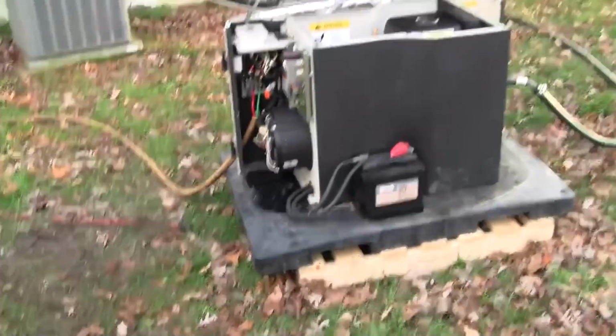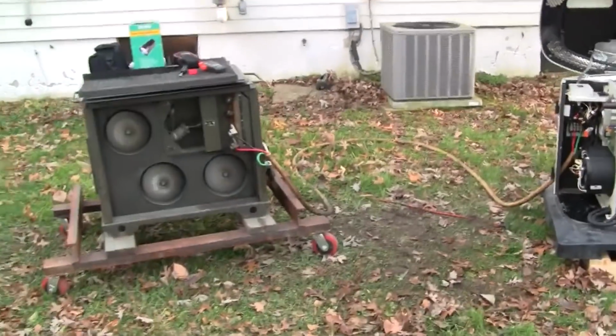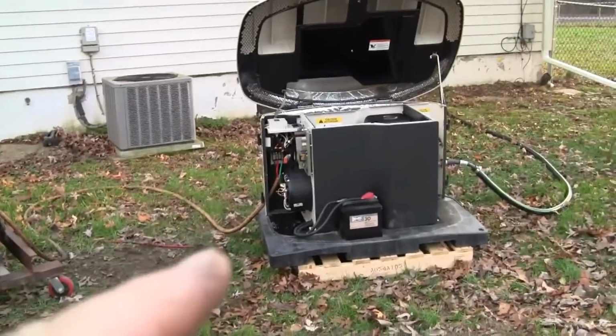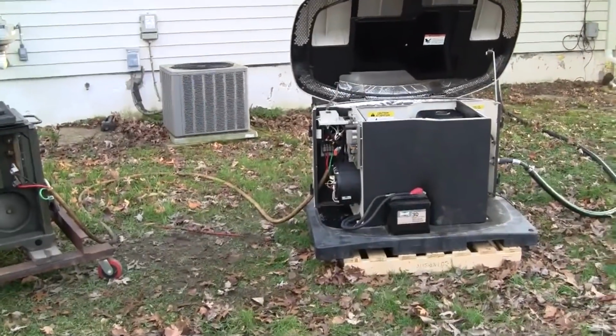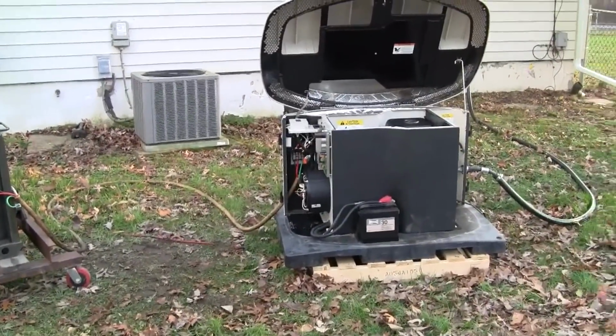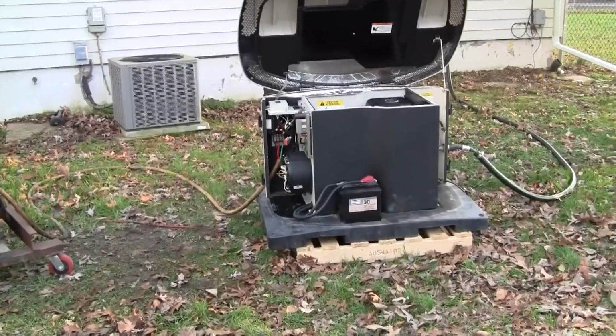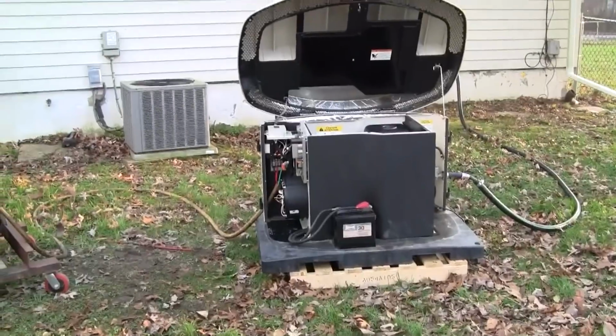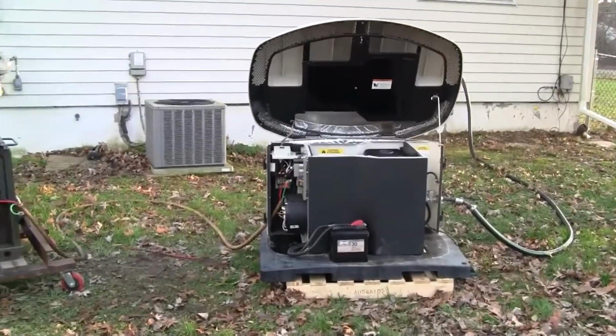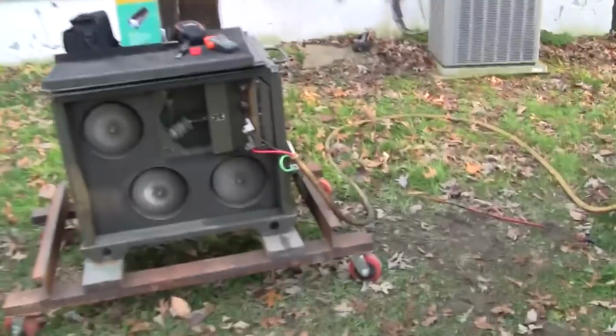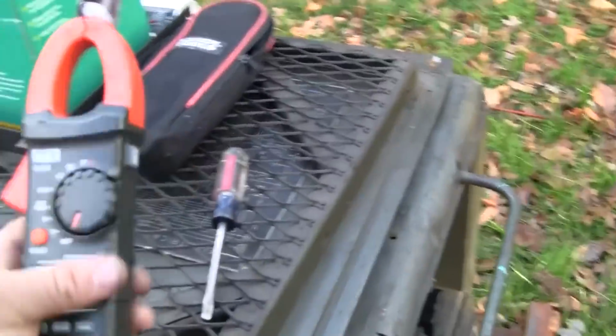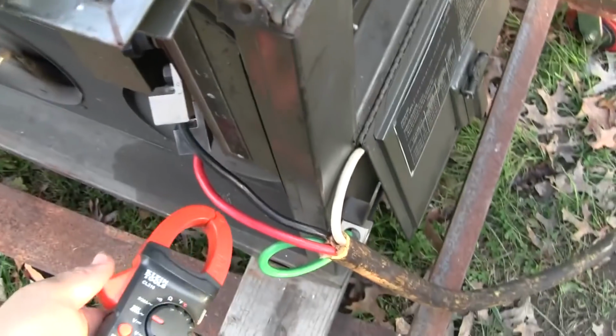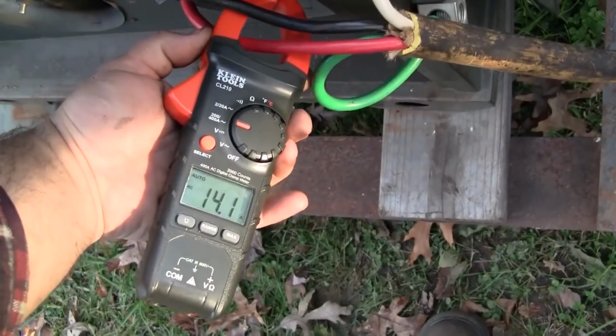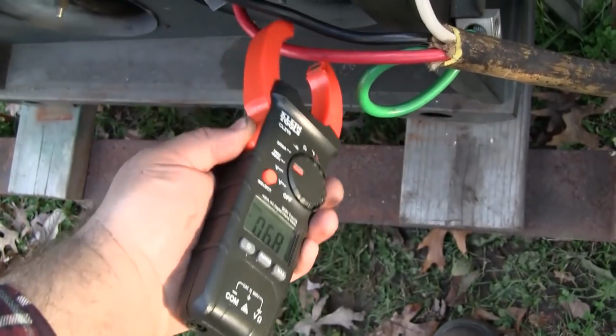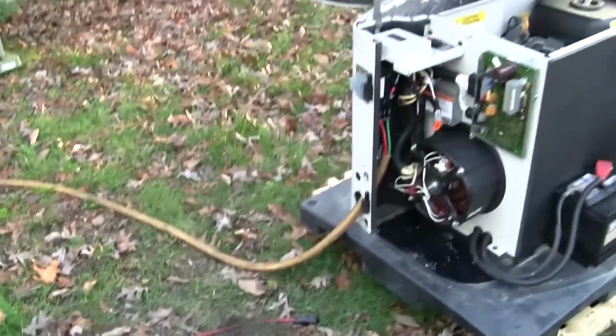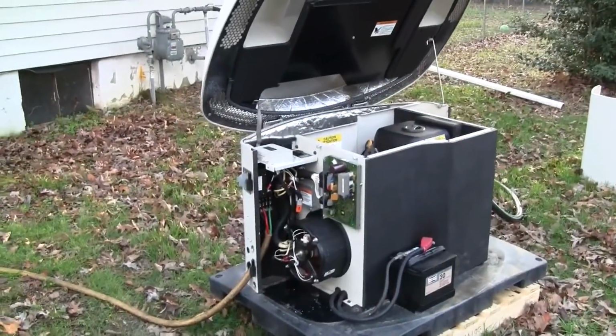So like I said, this is a 20 kilowatt generator. My load bank is loading both sides, both windings of that generator equally. It's running 240 volts. Now, 20 kilowatt at 240 volts is 83 amps, pretty much 83 amps on the nose. So we know that's our target for full load operation. Let's see, 3 kilowatts, that's where we're at right now. There, I only put 14 amps on it. We'll be nice and let it warm up at 3 kilowatts for a few minutes.